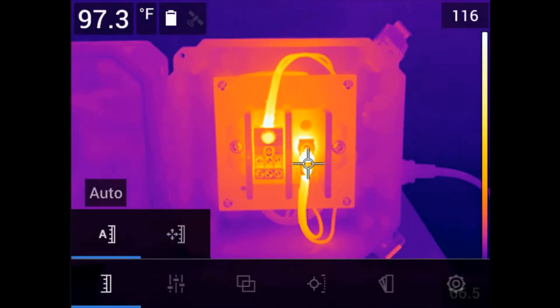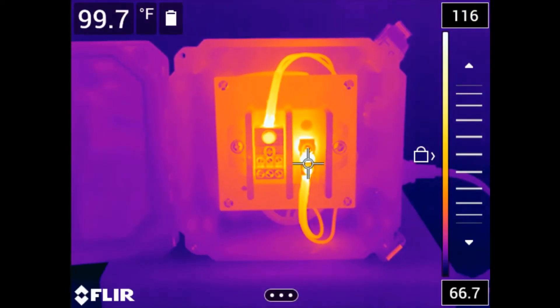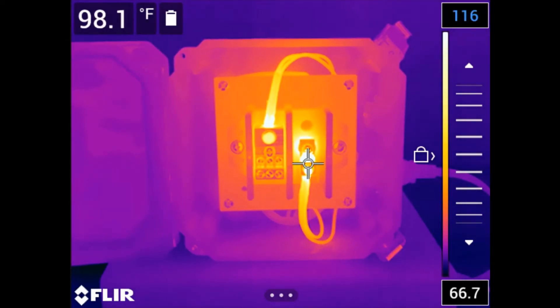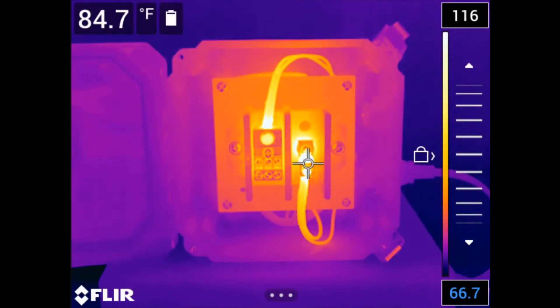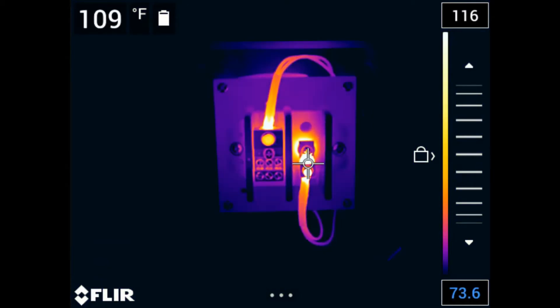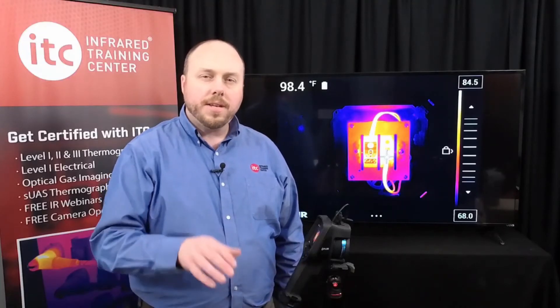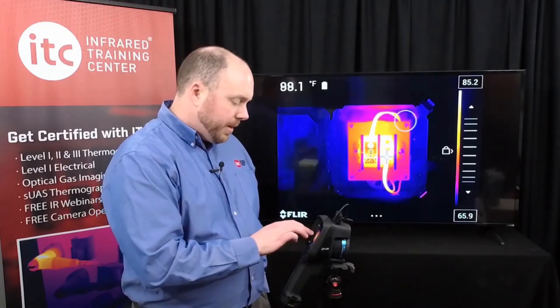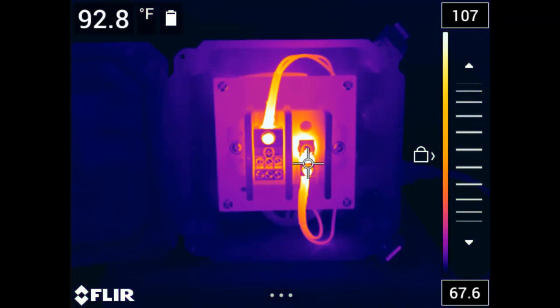To manually adjust the image, go to the main menu and select the temperature scale icon on the main screen. Pressing the center push button will display two choices: Automatic and Manual. Selecting Manual allows you to customize the scale settings. Press the navigation pad left or right to pick either the top or bottom number on the temperature scale — the selected number will turn blue. Pushing up or down on the navigation pad will change the value. Bring the numbers closer together to narrow the span and increase contrast, or push them further apart to widen the span and decrease thermal contrast. When neither number is selected in manual mode, pushing the navigation pad up or down changes the level of the image, leaving the span fixed but shifting it within the camera's range.